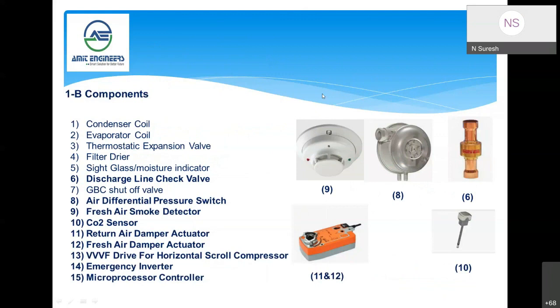Here I'm not going to cover in detail the basic refrigeration components. I'm going to cover the components newly added in the HVAC system, in the railway HVAC system for Indian Railway, this project. One is the discharge check valve, which is fixed in the discharge line of the horizontal scroll compressor. The second is the air differential pressure switch, fixed to check whether there is any pressure drop across the filter. If there is an indication, then we have to do the maintenance. I'll cover more detail in the coming slides.